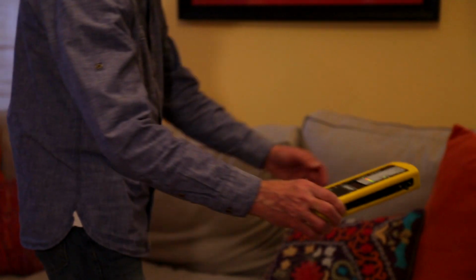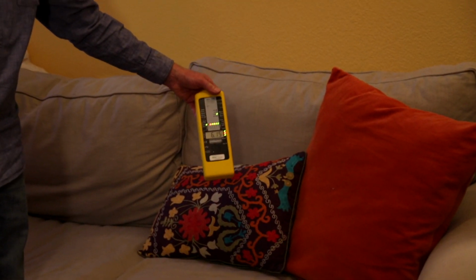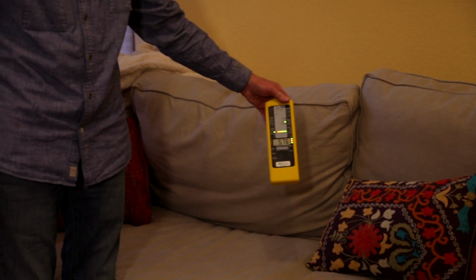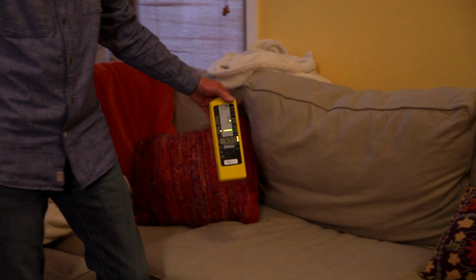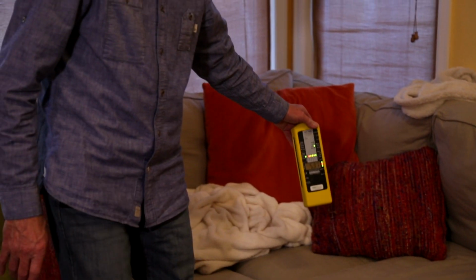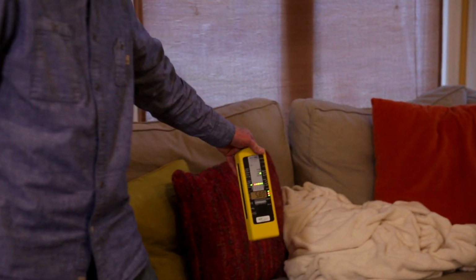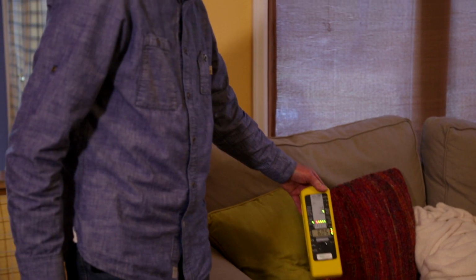We've placed a load on the outlets in the house looking for miswiring or parallel neutral paths, and we seem to have found one. So we're here in the family room with the meter just to show the effect that these sorts of things have on the level of field. So if we come over to the area where people are sitting on the couch watching TV or conversing, we're noticing we're running a 5 milligauss field, roughly 500% higher than the level we'd like to see people at in the areas where they rest and play. So 5.8 milligauss.